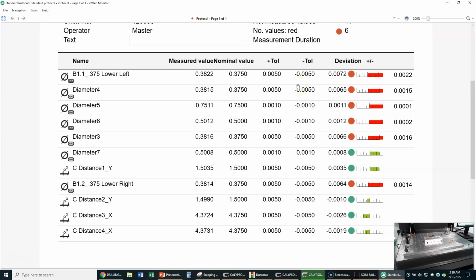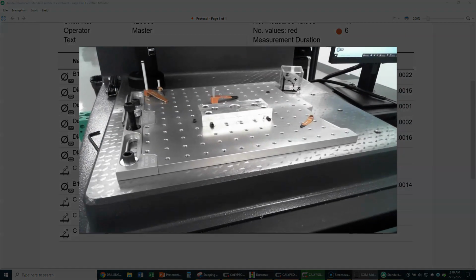Simple enough, right? Basically, update the names, check your nominals and tolerances, and then we have to make sure that we're not taking bad hits on our CMM. So right now we're making the assumption that the probe we're using on our CMM has been calibrated correctly, but what happens if somebody comes over and whacks this probe into something pretty hard? I was going to demo it for you, but I don't want to break it. But if somebody drives into that real quickly, is the probe still calibrated?